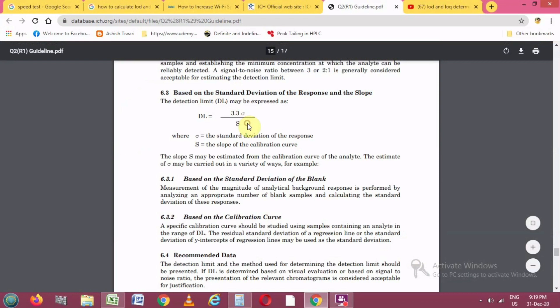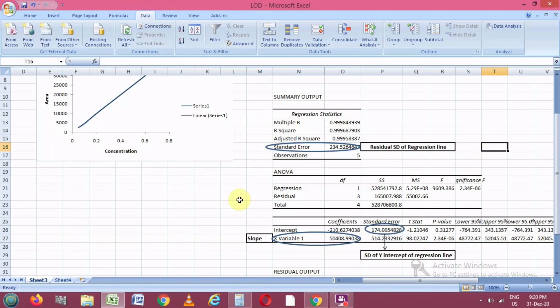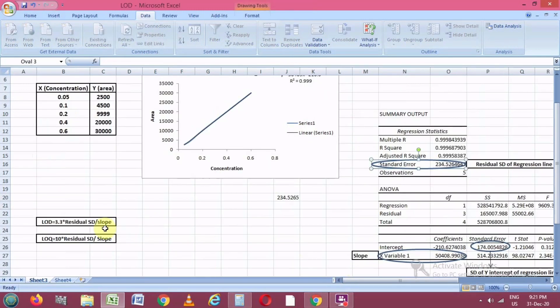Now coming back to the ICH guideline, the formula for detection limit is 3.3 × sigma divided by S, where S is the slope and sigma is the standard deviation of response. In section 6.3.2, based on the calibration curve, a specific calibration curve should be studied using samples containing analyte in the range of the detection limit. The residual standard deviation of the regression line or the standard deviation of the y-intercept may be used as the standard deviation — not the normal standard deviation, but the standard error values for x and y axes.